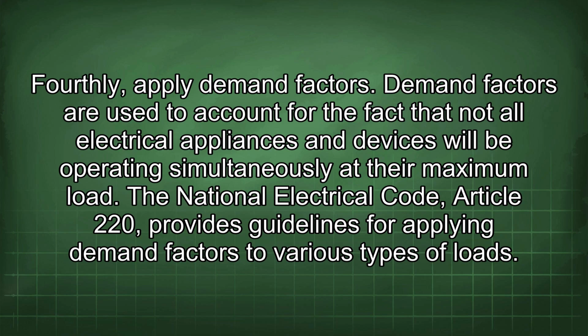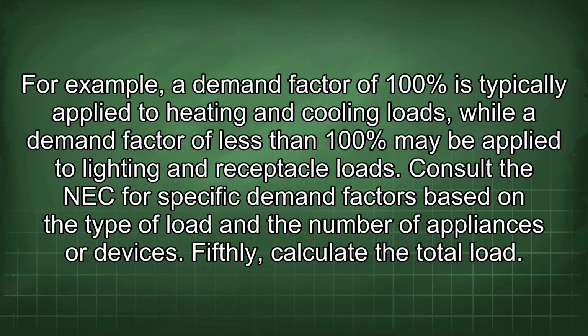Fourthly, apply demand factors. Demand factors are used to account for the fact that not all electrical appliances and devices will be operating simultaneously at their maximum load. The National Electrical Code, Article 220, provides guidelines for applying demand factors to various types of loads. For example, a demand factor of 100% is typically applied to heating and cooling loads, while a demand factor of less than 100% may be applied to lighting and receptacle loads. Consult the NEC for specific demand factors based on the type of load and the number of appliances or devices.